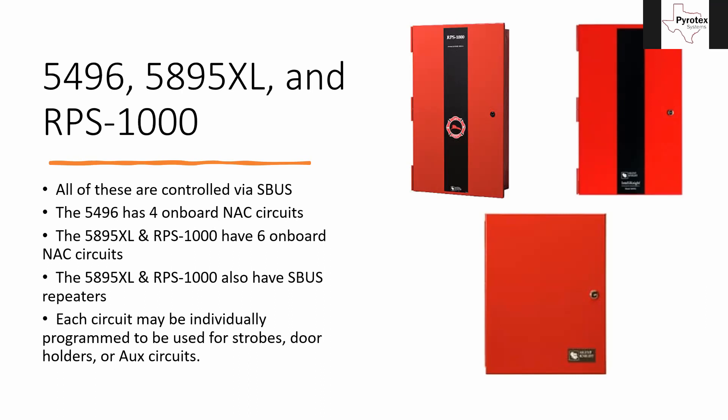One more note: I didn't put a slide in for the 5495 panel. It's the exact same cabinet as the 5496 and everything about it looks the same, except when you look at how it's triggered. The 5496 has terminals for SBUS, while the 5495 does not — the 5495 has a conventional input because it's a conventional power supply. The only difference between the 5495 and the 5496 is the 95 is conventional and the 96 is intelligent.